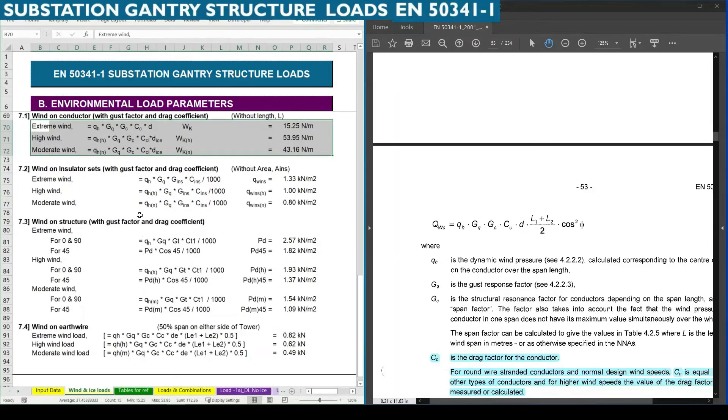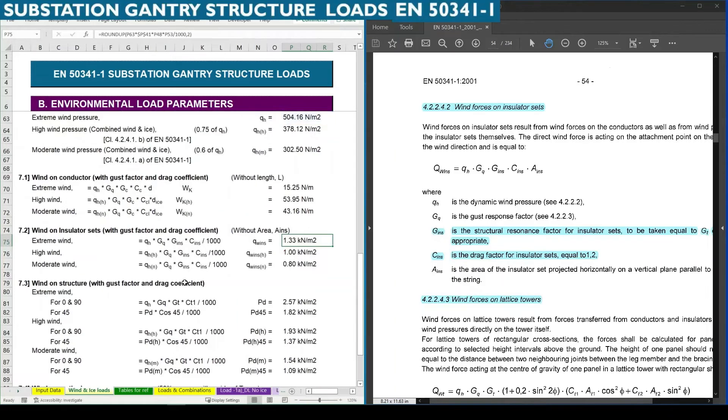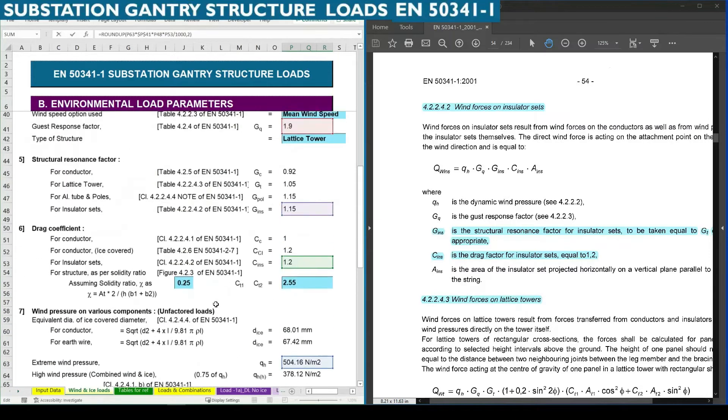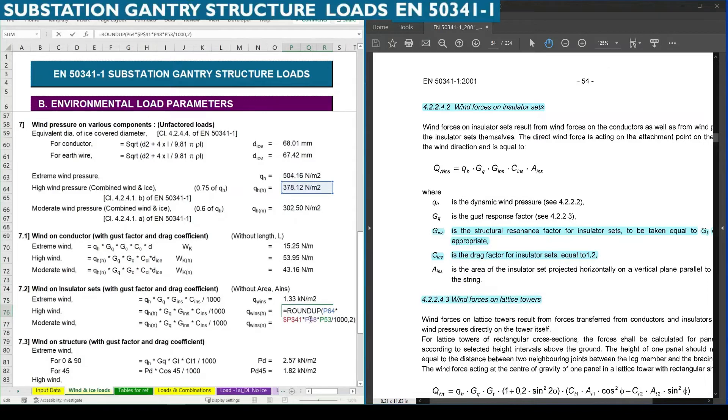Why does the value increase here? Because in high wind and moderate wind we need to consider the diameter as equivalent diameter of ice covered diameter. So D ice to be considered. If we consider D ice, it is 53.95 Newton per meter. Similarly for moderate wind, we need to consider D ice as the diameter of conductor. Finally we found the wind force per meter on conductor. Next is wind on insulator. For that this formula is on page number 54. Here you can see, except the area of the insulator, we are calculating the value. It means we are calculating the pressure by multiplying all the factors: gust factor, resonance factor, and drag factor with the wind pressure. Same for high wind pressure and moderate wind pressure.